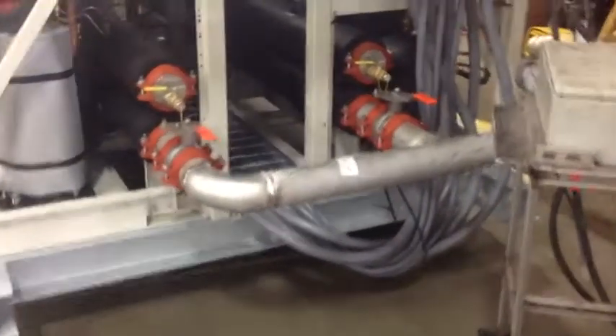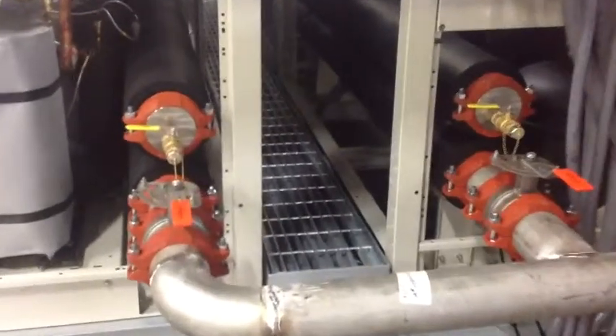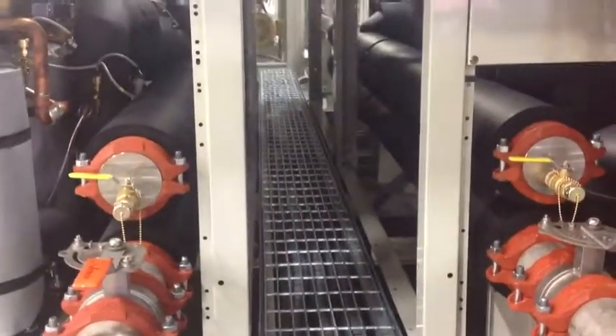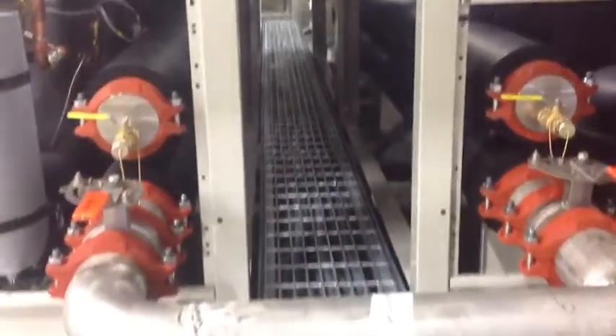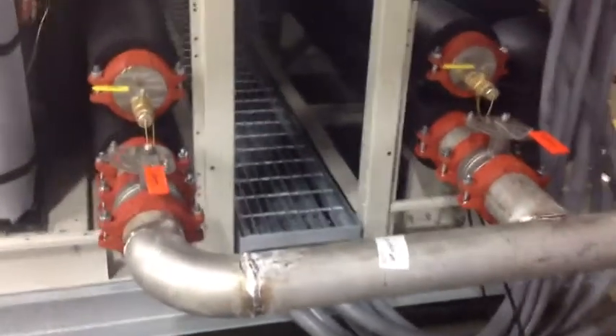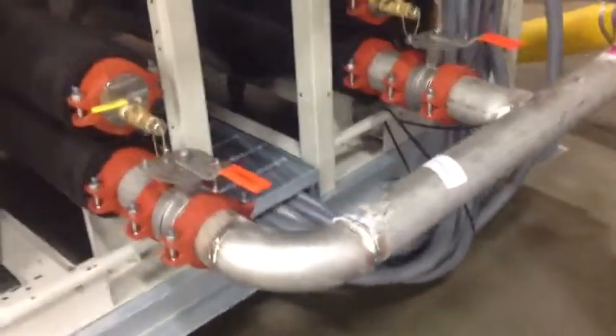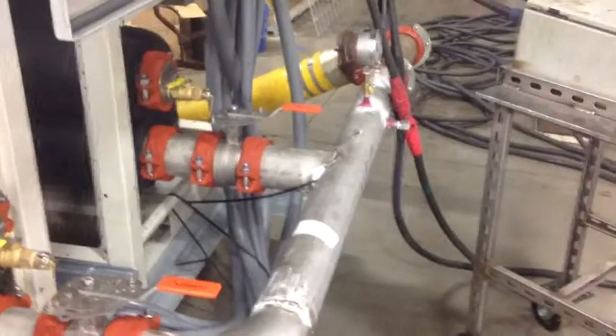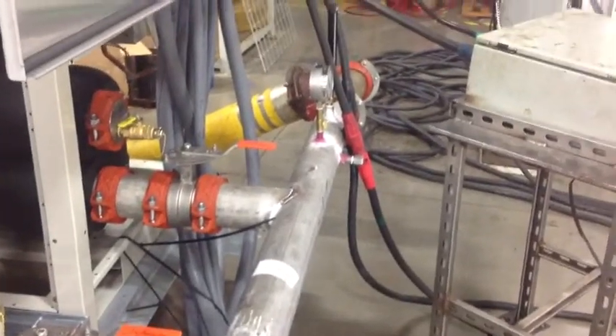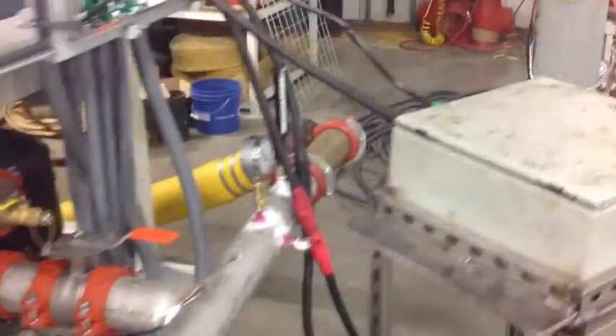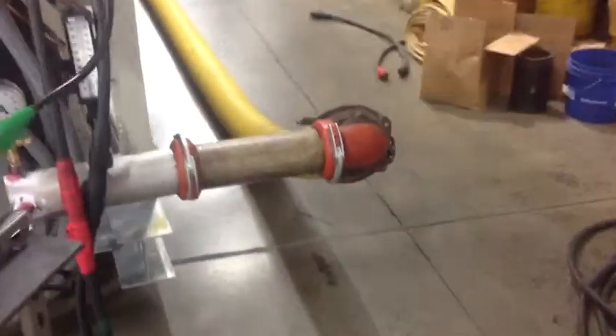As we zoom into the header piping that connects the front and rear modules, you'll see that there are isolation valves so that we can isolate the front modules from the rear modules. Now we zoom over to see the chilled water leaving connection, which has gauge taps as well as a leaving water temperature sensor tap.